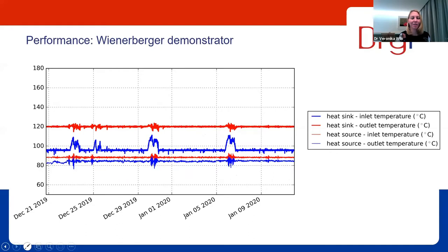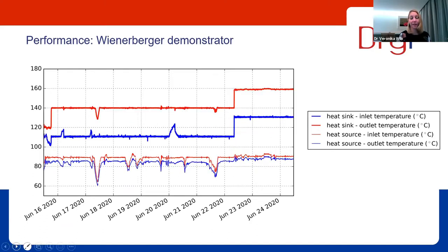And an interesting observation are these peaks that occur at the beginning of the week. So they are coming from the brick drying process. And we see the answer of the process control levels out these episodes. And this is an insight into operation of high temperature. So this is from June, also last year, when we had a longer period of operation at 160 degrees C. And yeah, here we also see some fluctuations in the heat source, but stationary behavior of the heat pump.